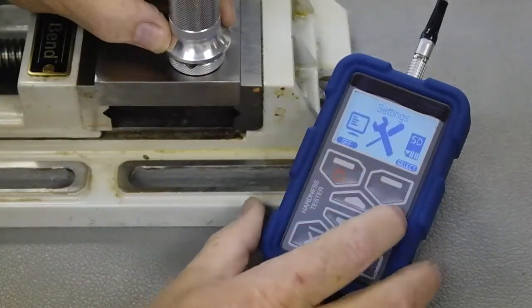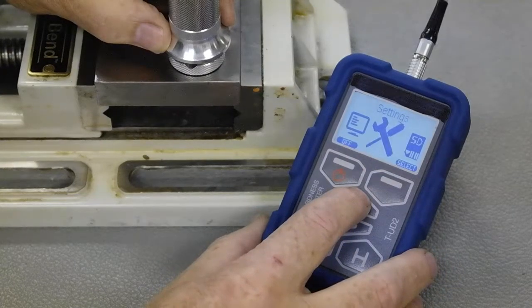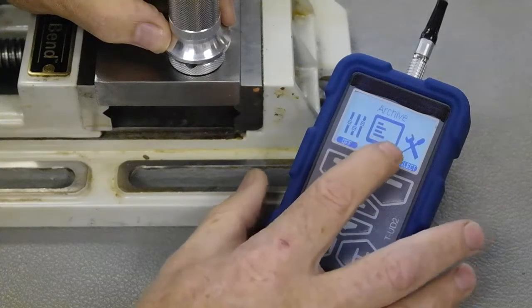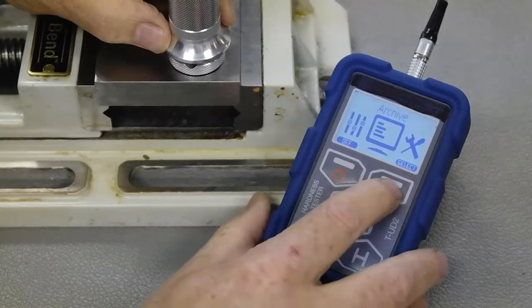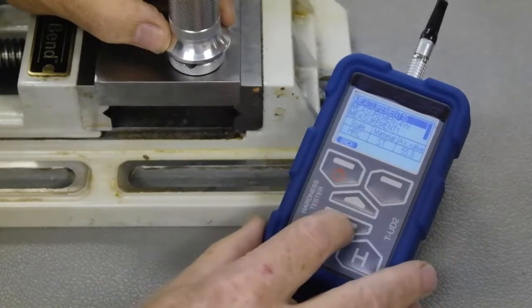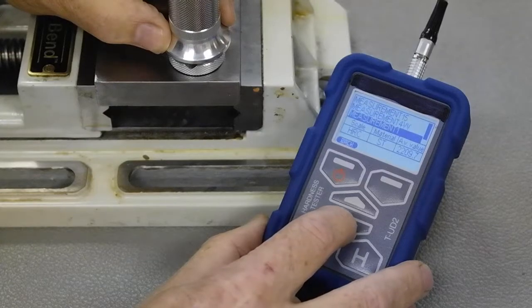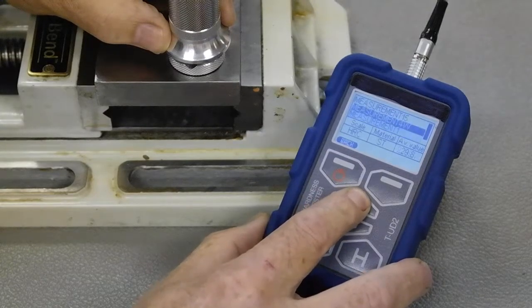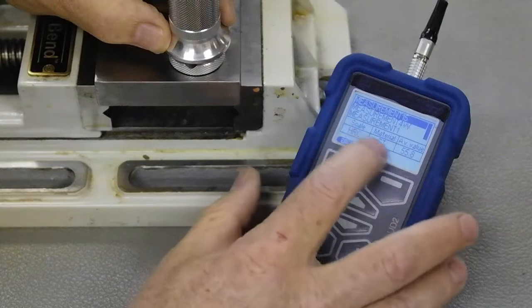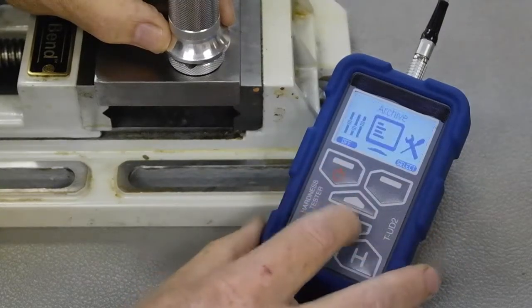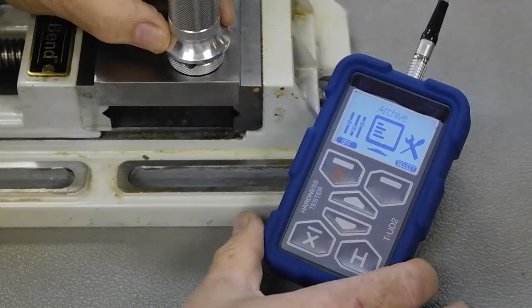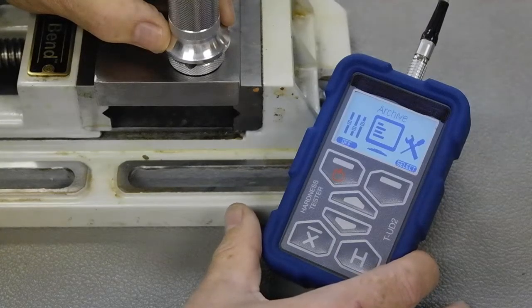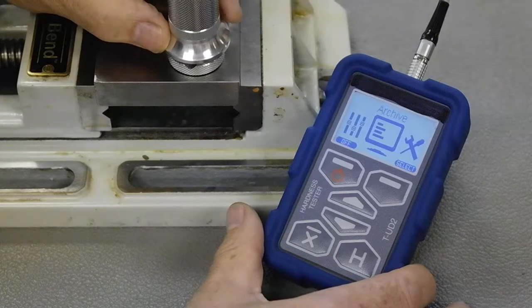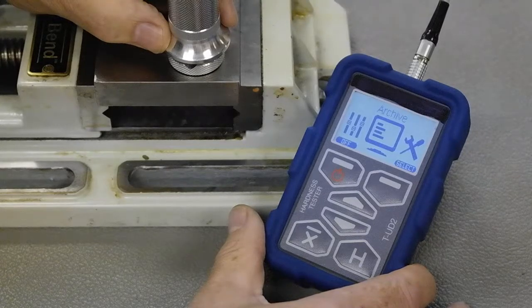Other settings through this display are archive, so we can look at all the prior tests. I do have some inside the system — you can see here these are the prior tests I've done, with each of the values and the average, what the material is, and what the scale is. These are all uploadable to a PC, and we have a special program for that where you can further upload to a spreadsheet and modify the data. We include the software and the cable to do that.